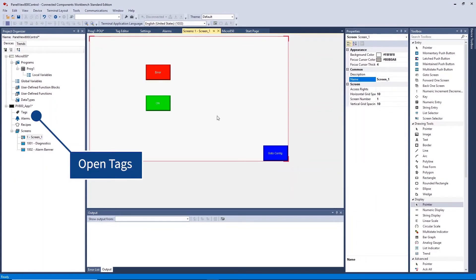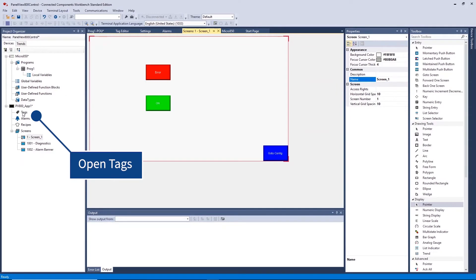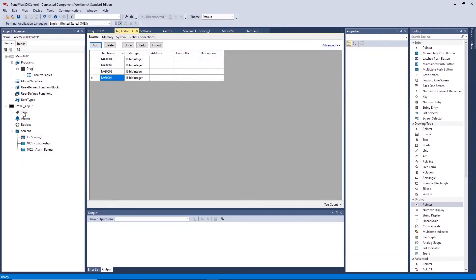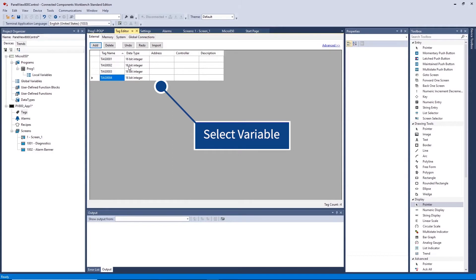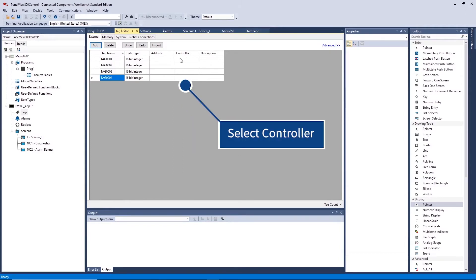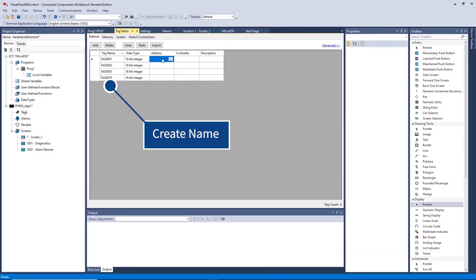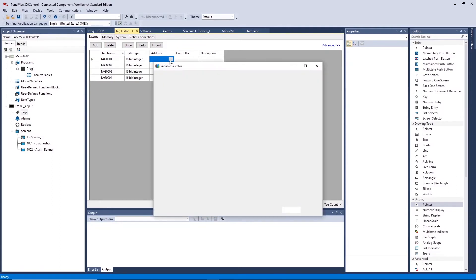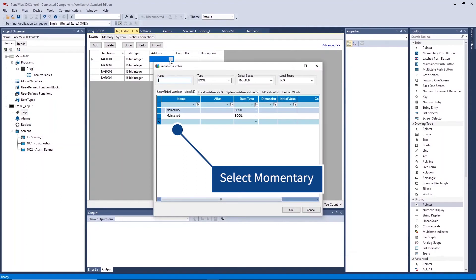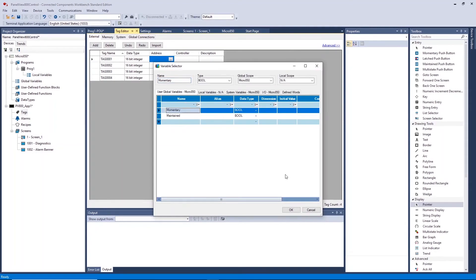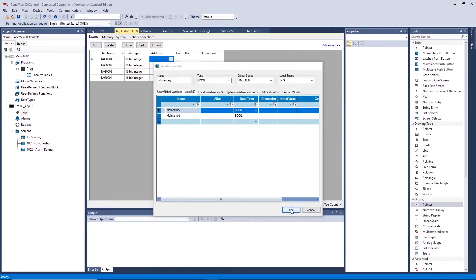Double click Tags. To create each tag, you will need to fill in the following: Address specifies which tag to reference to. Controller specifies which PLC to reference. Tag Name allows for renaming of the tag referenced via the HMI. We will set up two tags for the buttons we want to create and two output references that we will use in our ladder diagram.